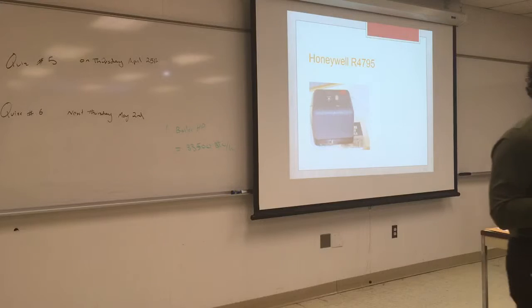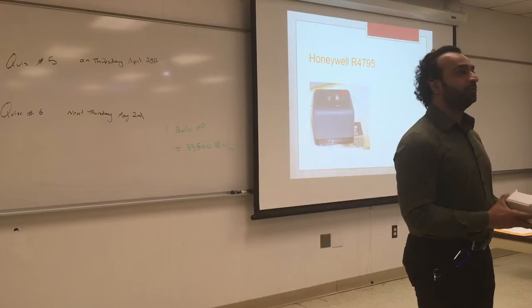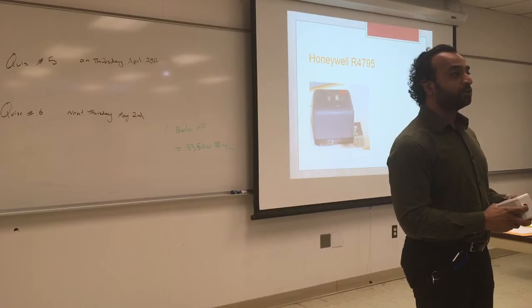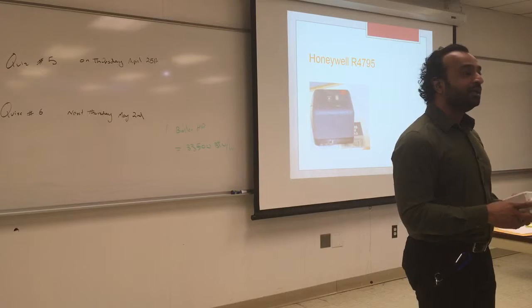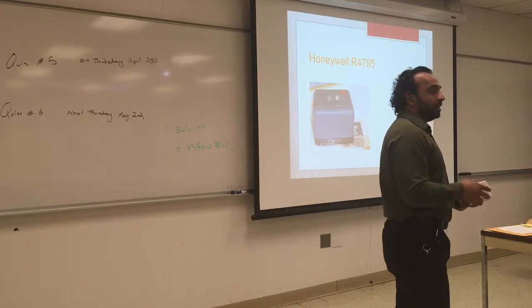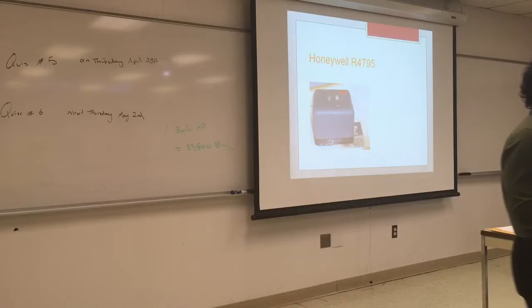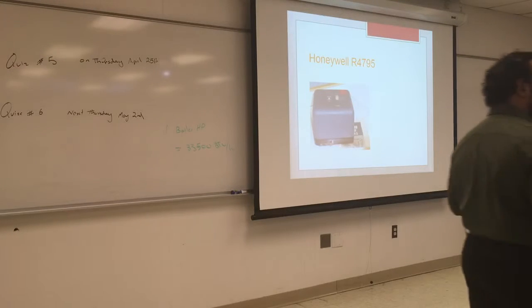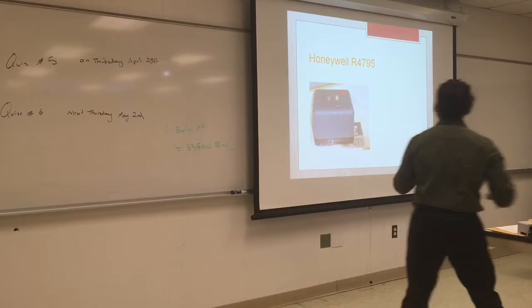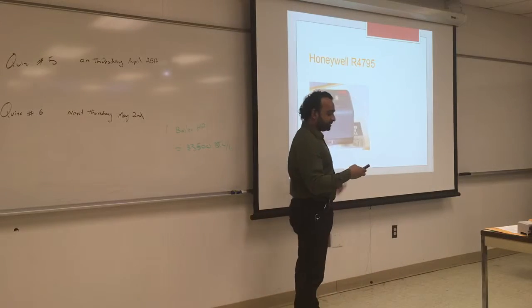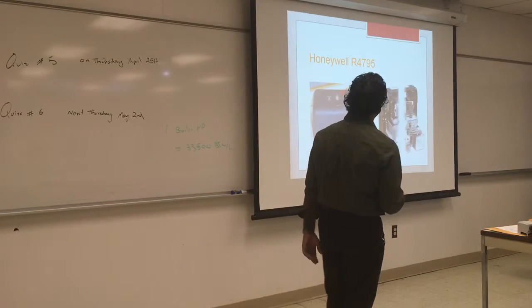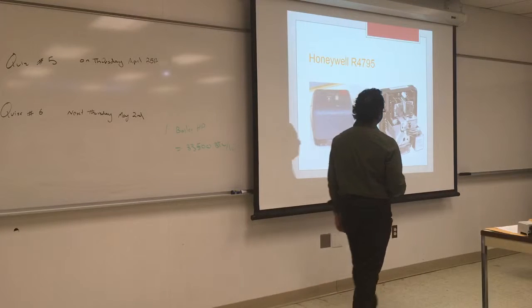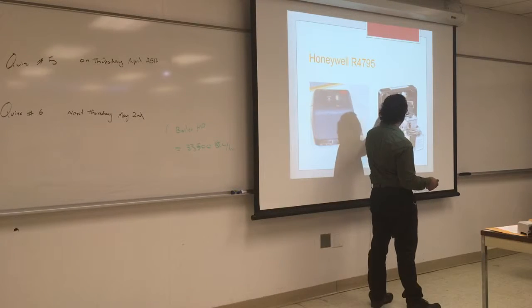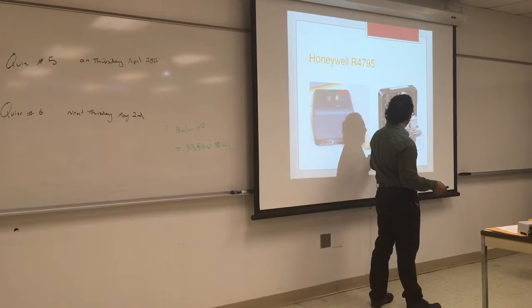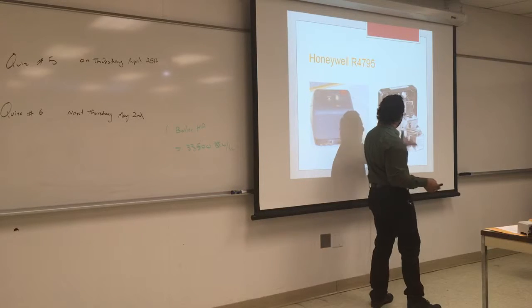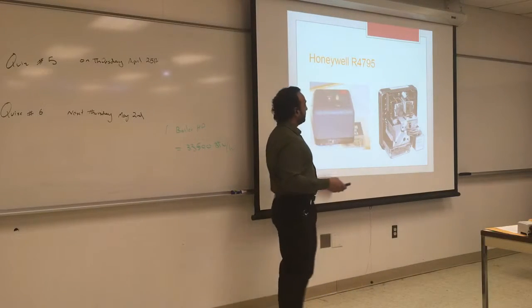The reason for that is to minimize the wiring and unwiring. You probably have noticed from the boards that screws get loose after a while. The connection can get loose. The wire can get fatigued, so you don't want to wire and rewire a lot. So this is one of the reasons why it comes in a box, and the base is always wired. This is what it looks like from the inside. The base is already bolted into the boiler, and this is if you take out the top cover.